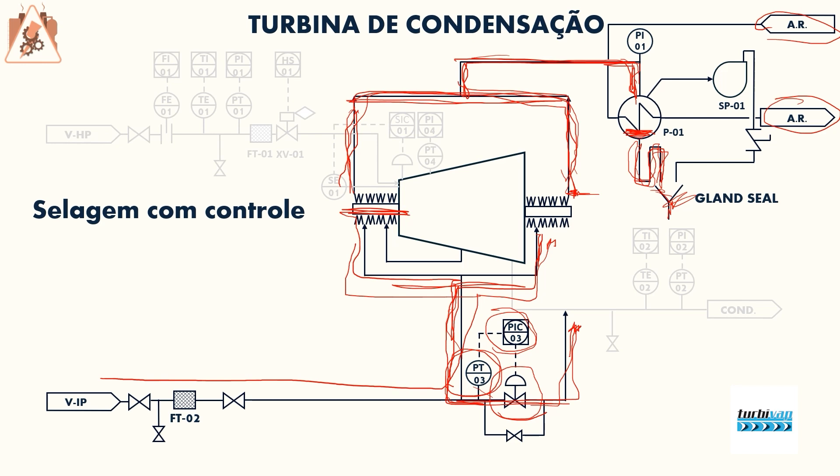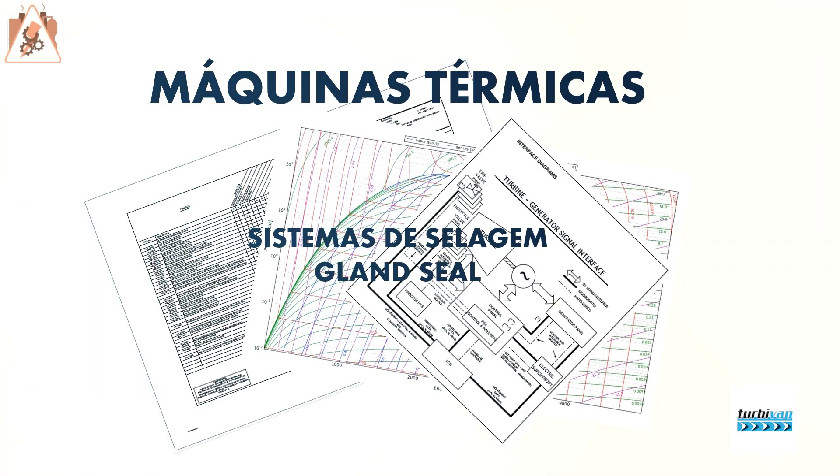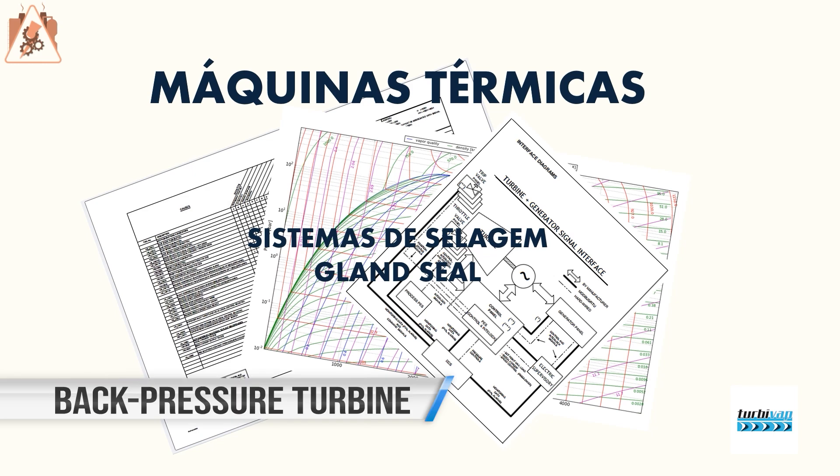API 612 requires that a condensation system be introduced into the turbine to prevent steam from contaminating the lubrication bearings. The non-condensables are then separated inside the exchanger and directed to a vacuum pump or an air blower.